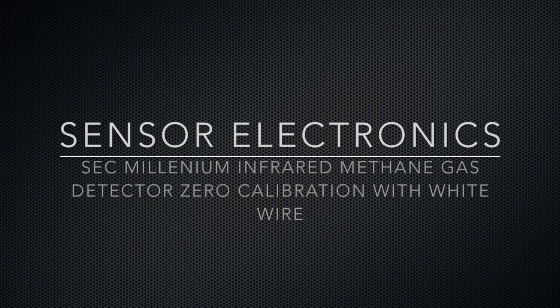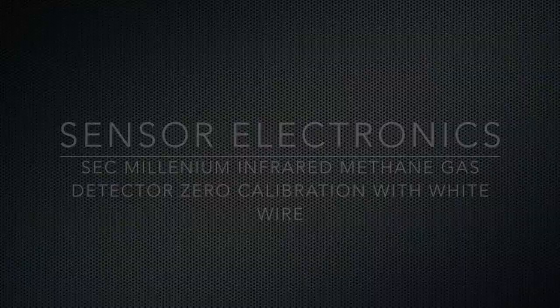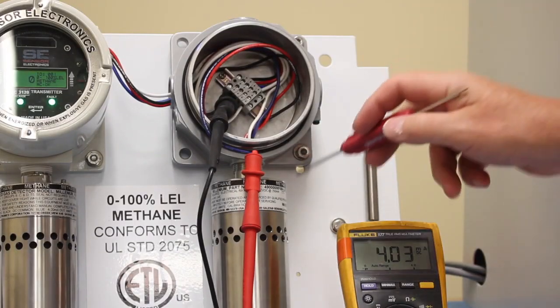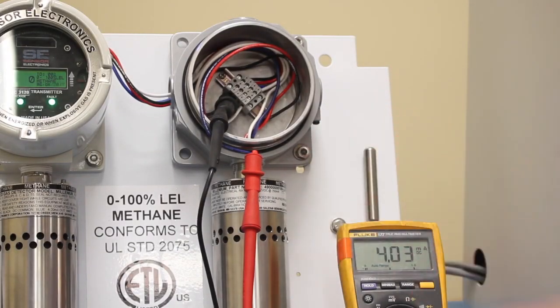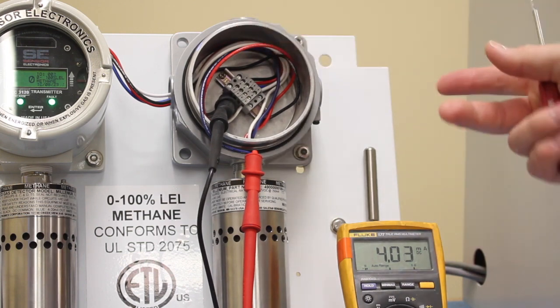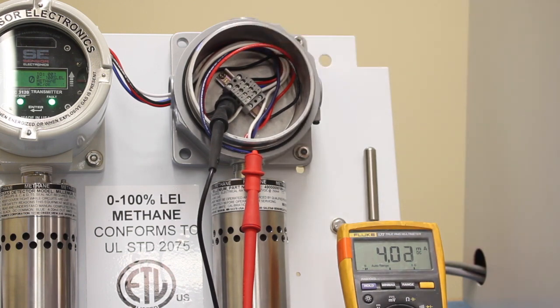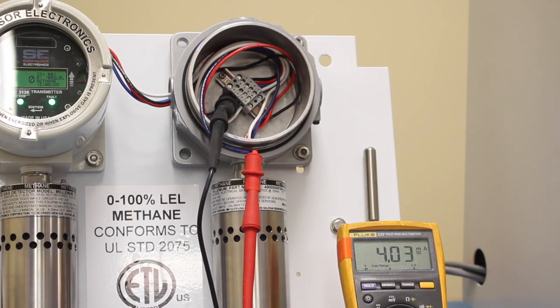Calibrate the SEC Millenium sensor to what we call a hard zero. Since the Millenium sensor is a standalone sensor, it can be used without a transmitter, and it provides a 4 to 20 milliamp signal into a PLC or some type of control panel. Right now I've just got the current coming into the meter to demonstrate the zero calibration procedure. And how you calibrate it without a transmitter is quite easy.